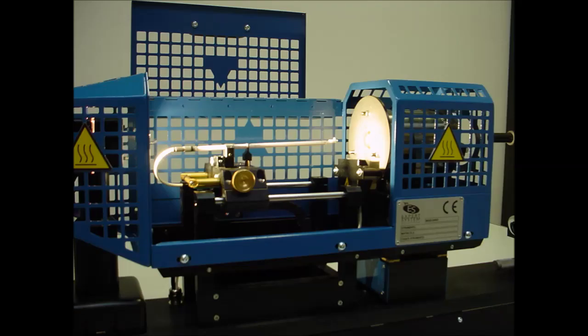The specimen is positioned on a sample holder rod and it is inserted into a tubular kiln. MISURA HSM is available in several versions with a heating rate up to 80 degrees centigrade per minute and up to a maximum temperature of 1600 degrees centigrade.